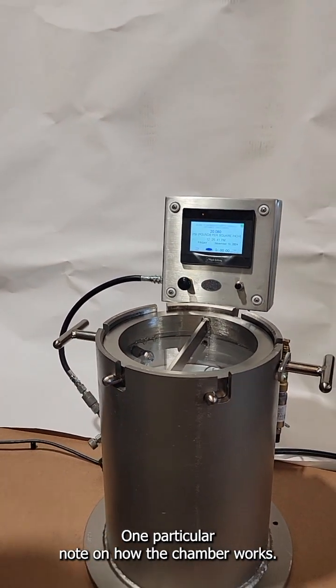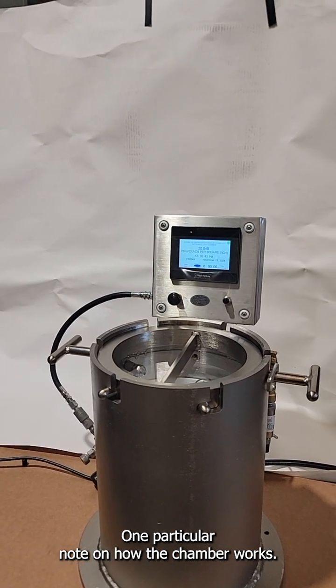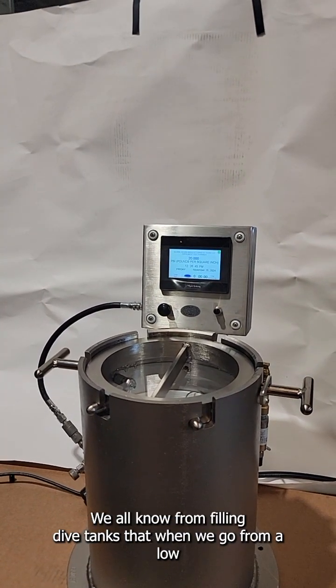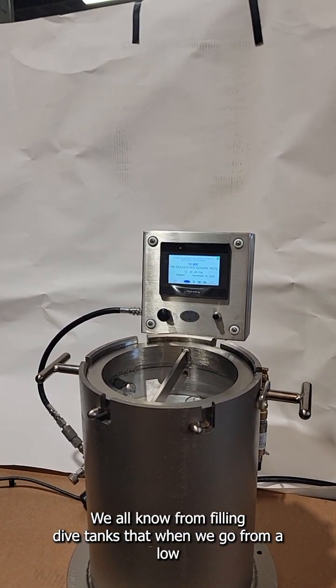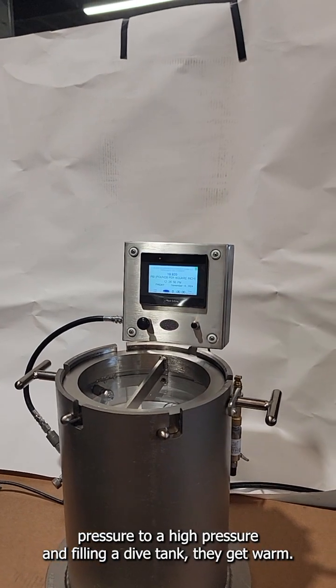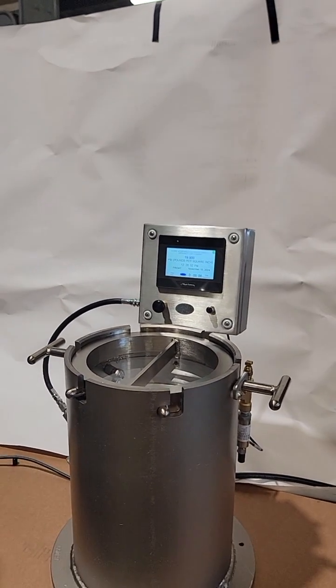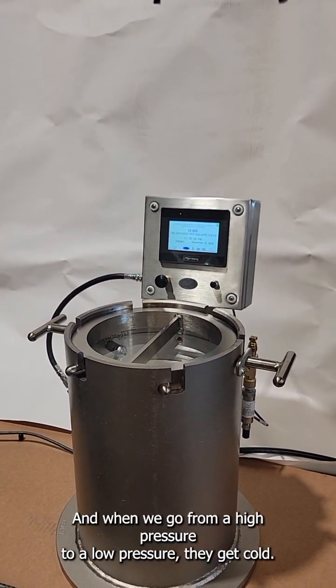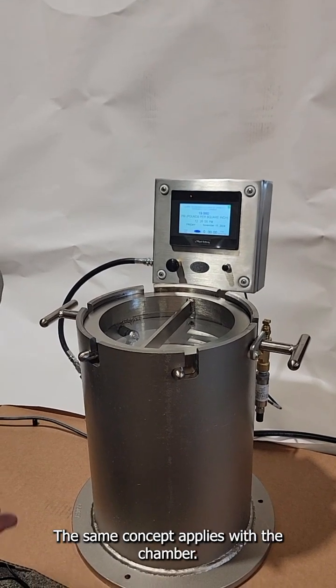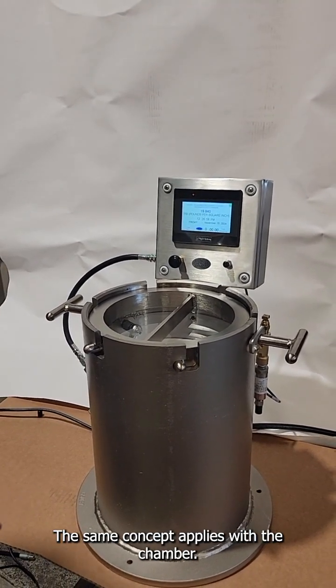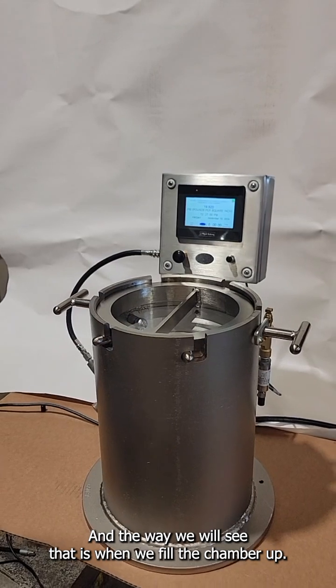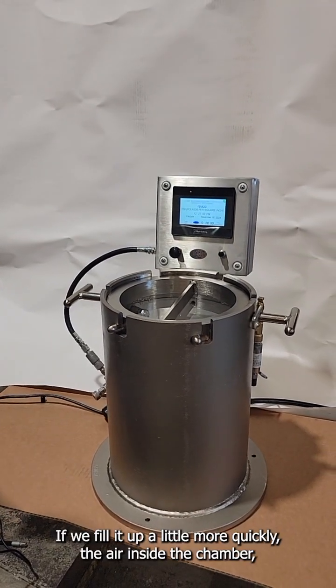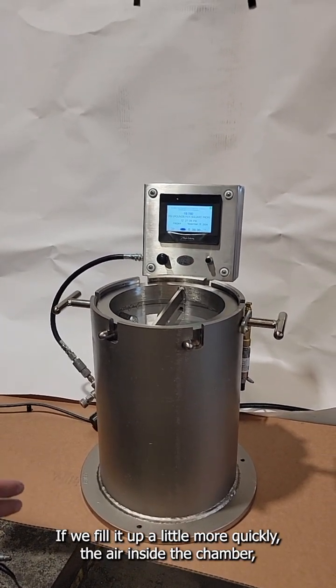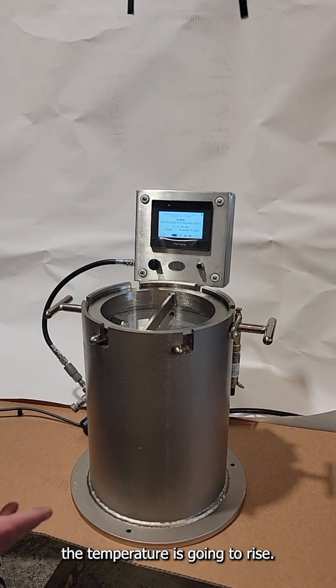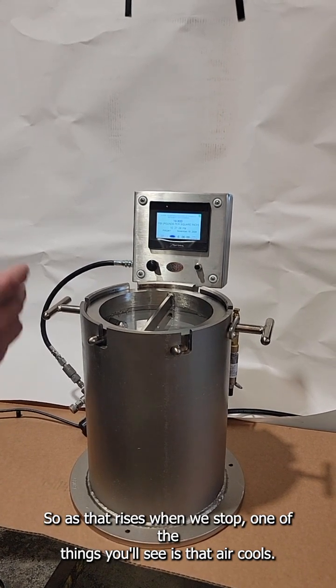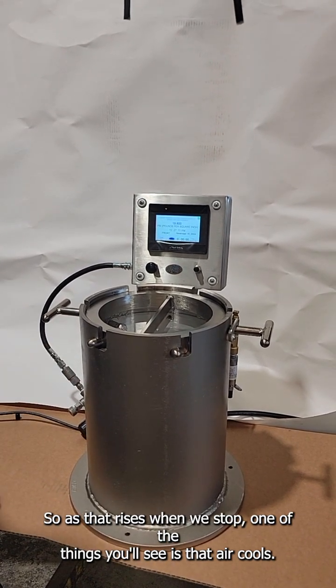One particular note on how the chamber works. We all know from filling dive tanks that when we go from a low pressure to a high pressure, filling a dive tank, they get warm. And when we go from a high pressure to a low pressure, they get cold. The same concept applies with the chamber. We will see that when we fill the chamber up: if we fill it a little more quickly, the temperature of the air inside the chamber is going to rise. So as that rises, when we stop, that air cools.